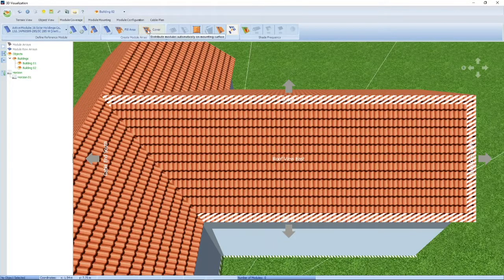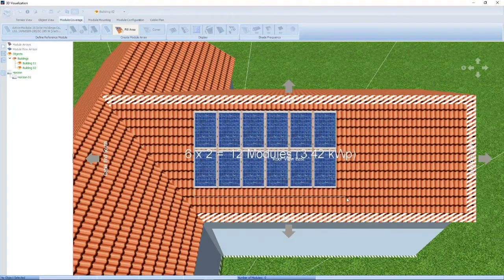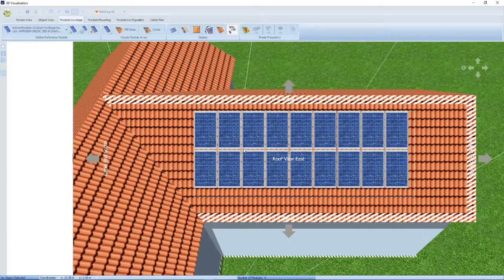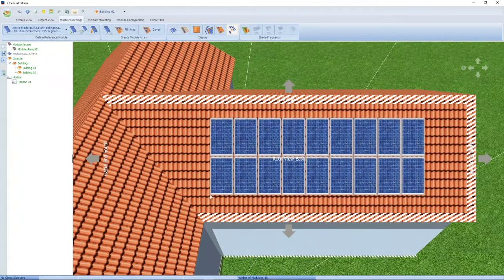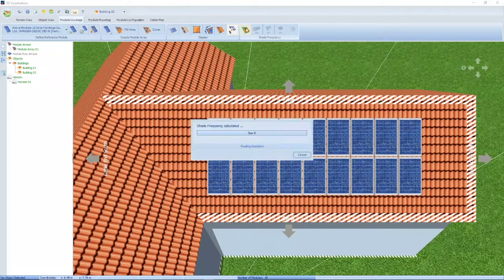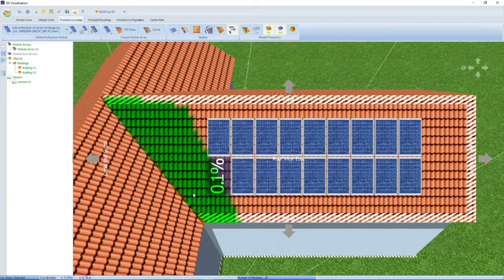Going back to module coverage, another way is to fill an area. Here you specify the horizontal and vertical distance between modules — normally that will be your clamp size. You can use your mouse and drag the number of modules onto your roof. In this case we're going to put about 5 kilowatt on. You can also move it around. You can do a shading analysis by clicking on the shade frequency — PV Sol will do a shading analysis over one full year and indicate per module any shading you might have. Here you can see one module will have a little bit of shading.